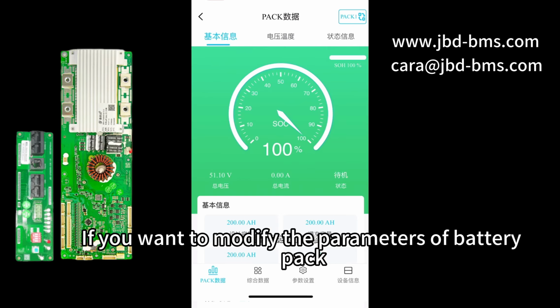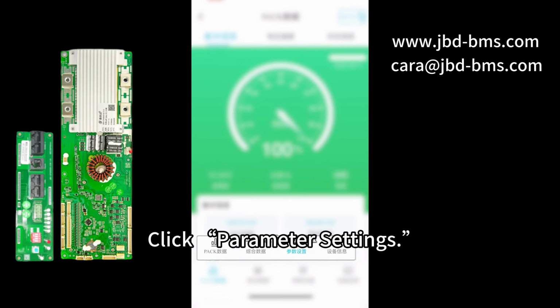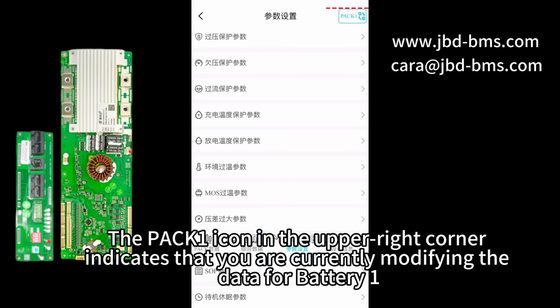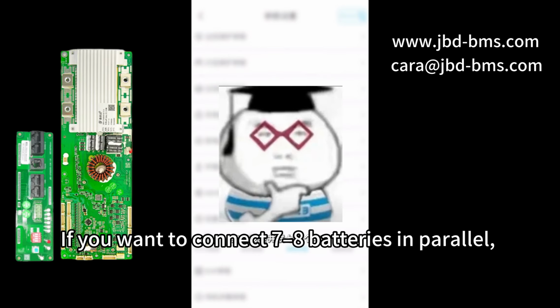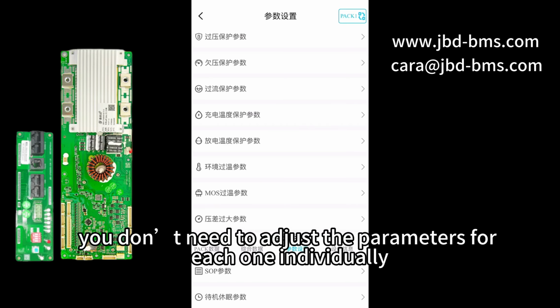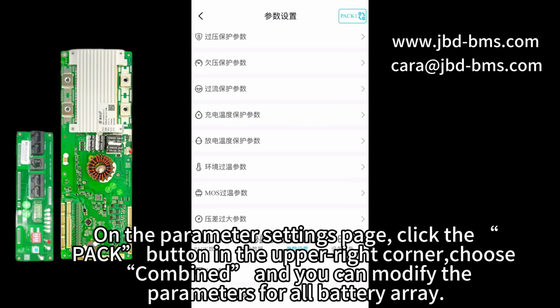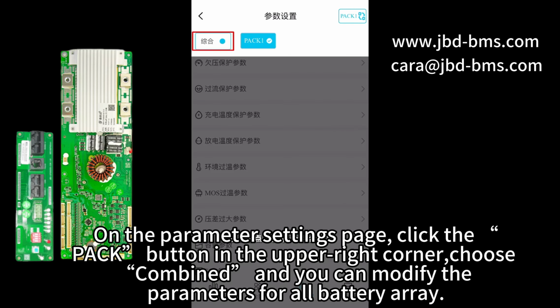If you want to modify the parameters of the battery pack, click Parameter Settings. The pack 1 icon in the upper right corner indicates that you are currently modifying the data for battery 1. If you want to connect 7-8 batteries in parallel, you don't need to adjust the parameters for each one individually. On the Parameter Settings page, click the Pack button in the upper right corner, choose Combined, and you can modify the parameters for all the battery array.